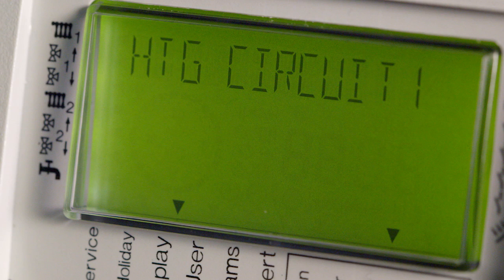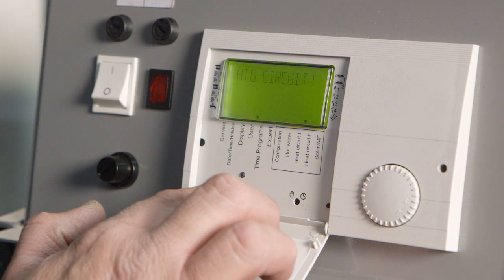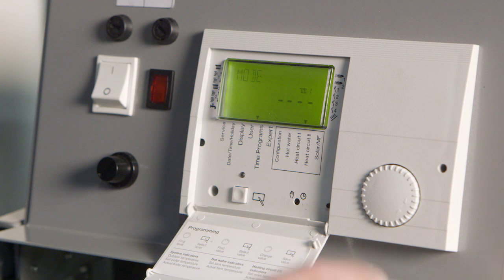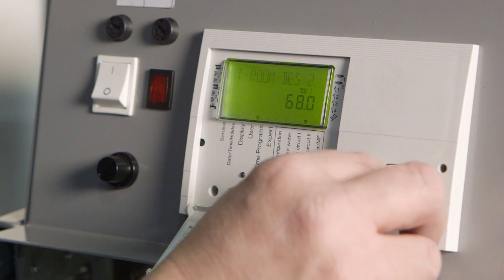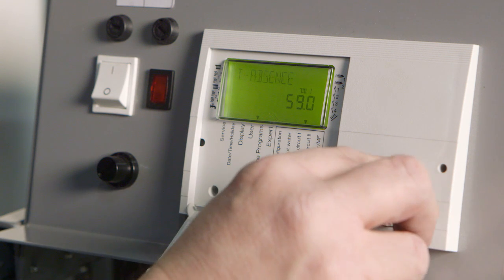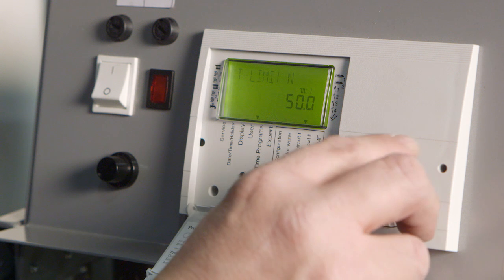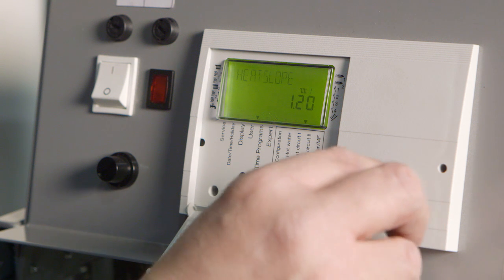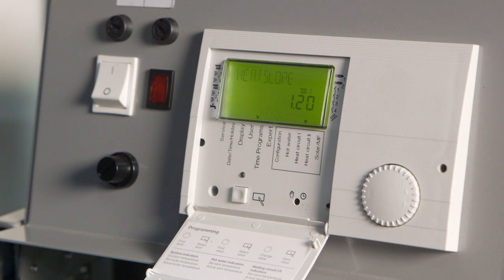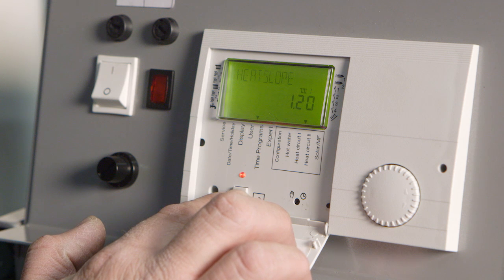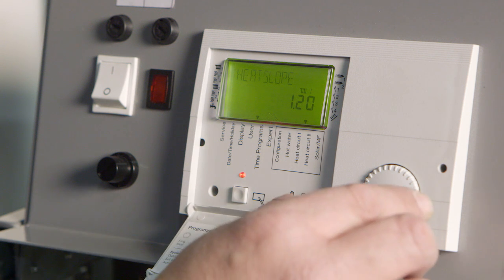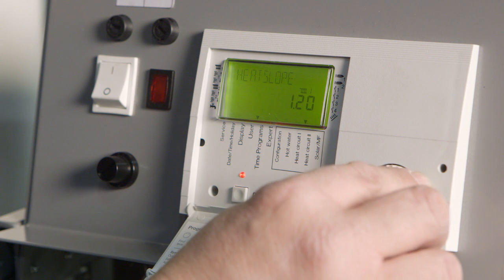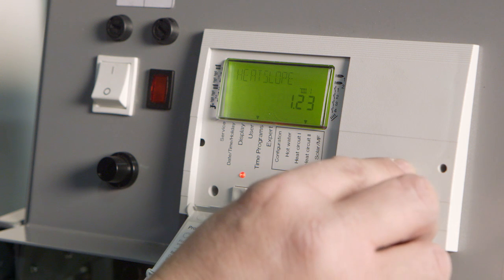To set the reset schedule, you must adjust the heat slope as shown. Press the program key. Turn the knob again to find the heat slope submenu item as shown. As you can see, the current value stored in the system's memory appears here. To change it, press the program key and the red light like this will appear. Now change the value according to the heat slope diagram that can be found in your manual.